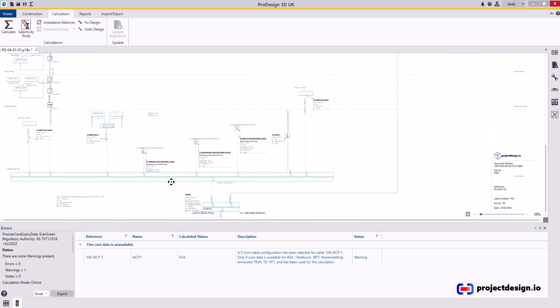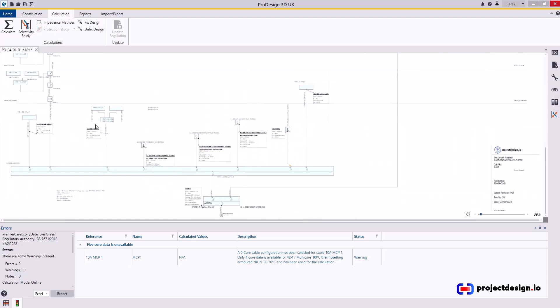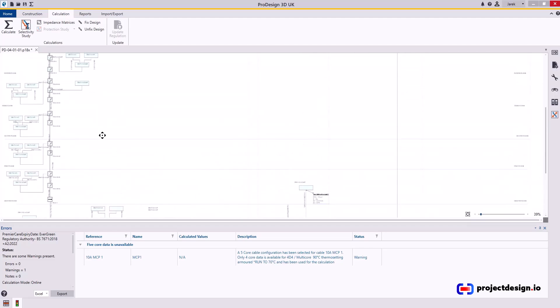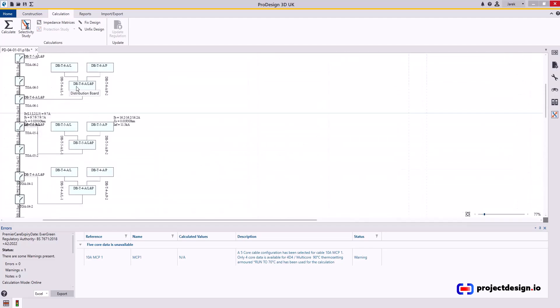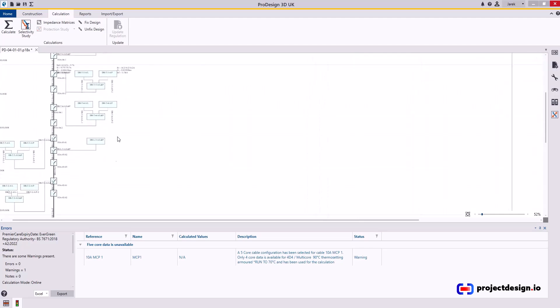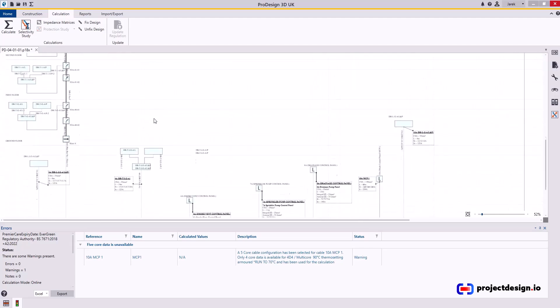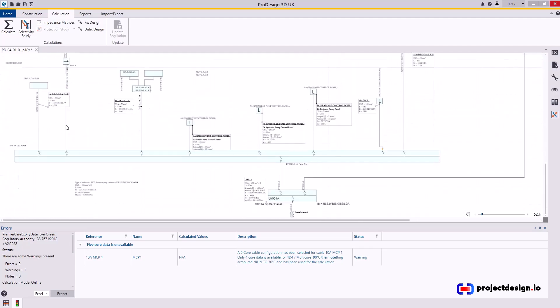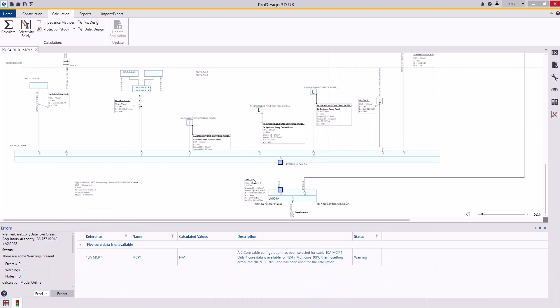First, we've done the calculations and we had the errors with protection being added to incomer where it shouldn't be. Then we had one of the cables here, which was undersized 35 mil instead of 50. Then when we've done a selectivity study, we had issue with discrimination between this cable and that cable. After we've managed to fix the selectivity between them two, I then had a problem with the selectivity between this cable and the origin. Once all of it was set, that's it. No problems. Now you can print your reports and submit your cable sizes for approval, including with the setting of the protective devices. Thank you very much for watching and I hope you enjoyed this video. Have a great day. Bye.